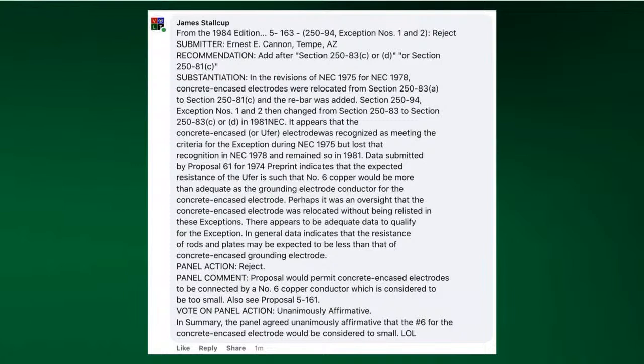Right. Then he says, perhaps it was an oversight that the concrete encased electrode was relocated without being relisted in these exceptions. There appears to be adequate data to qualify for the exception. In general, data indicates that the resistance of rods and plates may be expected to be less than that of the concrete encased electrode. And then they rejected what he was saying here.